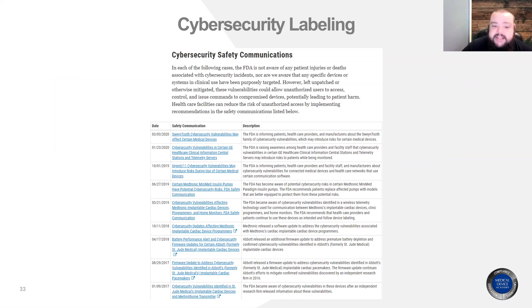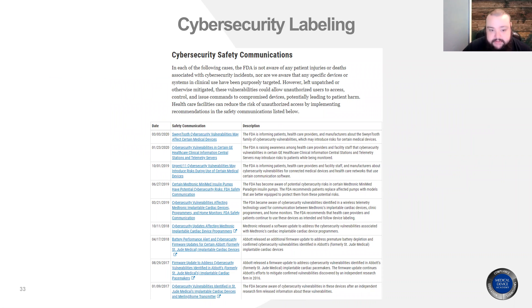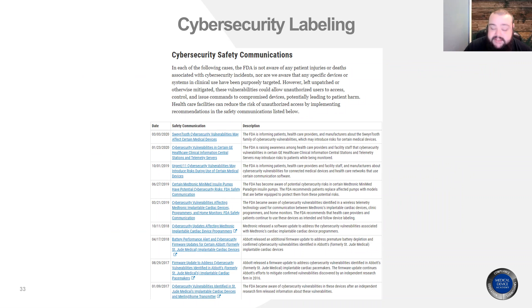Because our presentation today is specific to 510K applications, we can operate under the assumption that you have at least one predicate device that your device is substantially equivalent to in safety and efficacy. This isn't a breakthrough application — there are other devices already on the market similar to yours. The FDA has cybersecurity safety communications they release; leverage these for devices similar to yours to figure out what cybersecurity risks are applicable to your device.